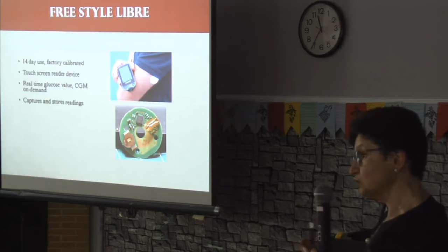Is that the same as whatever lag might be when you check with an actual meter? No, because with an actual meter you do the blood. So the question was if there is a lag time with the meter. No, because with the meter you check actual blood glucose, while with the sensor you check interstitial fluid glucose. Oh. Yeah. So the delay is between what you see on the meter and what's showing on the sensor.